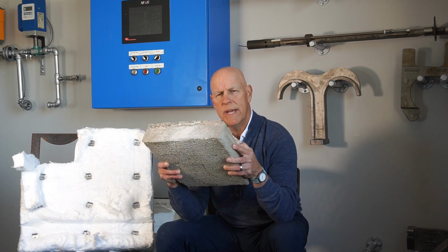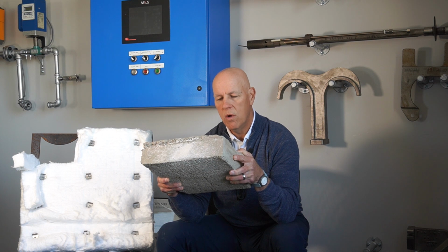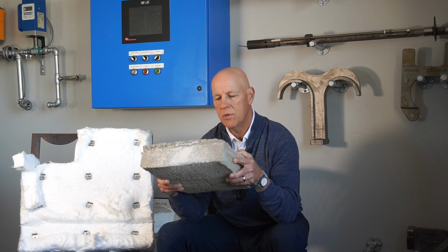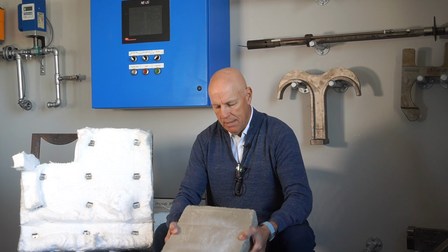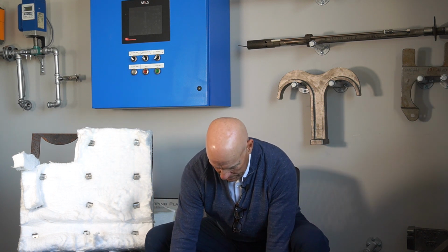Hard refractory, you see there's no visible anchors, but when you apply it, there's anchors actually on the wall, but they're embedded inside of it. So you have no anchor exposure. So hard refractory can take really high temperatures, really high velocities, and survive, but it doesn't like fast heat up. So that pretty much sums up refractory, and we would be happy to answer any questions you might have beyond what I've talked about.